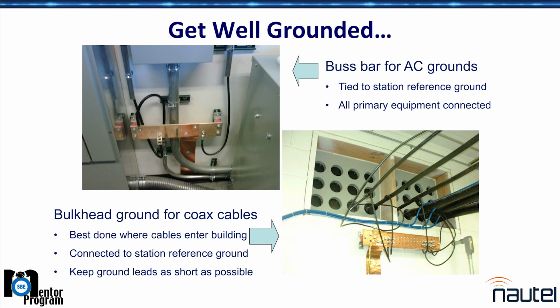Short and straight: when you're running a ground wire, if you come straight down to the top instead of looping, you've cut a foot off the length of that wire. Not only that, lightning doesn't do U-turns—well, it does if you hit it with enough of it, but there's a high frequency component, and you're adding inductance, which further increases the overall impedance of the cable.